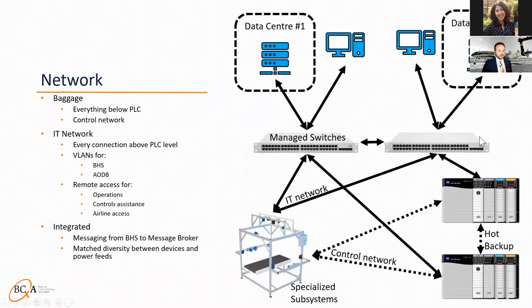Before going on to commissioning, all of the base building network needs to be operational so that the servers can be in their final location and that all of the networking can work correctly. In addition, there'll be remote access for airport operations people, controls engineers, and even airlines for porting access. This is all important to have before the main commissioning phase starts. In most new construction, this means that there needs to be a priority for building of data centers and communications rooms out in the field. In commissioning this, there's also integrated work that goes not just between these systems here, but also to external sources like message brokers and other services.